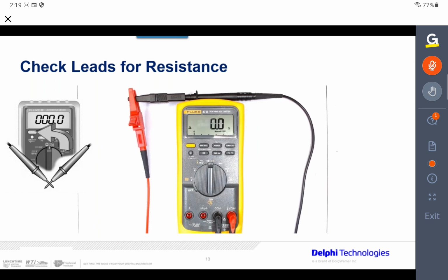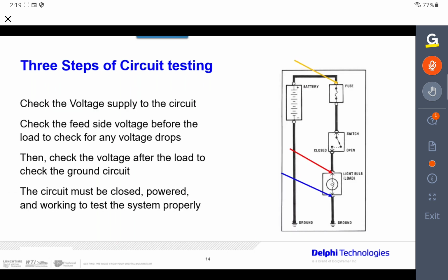The other thing you need to do is make sure the leads are connected together well and pushed into the sockets correctly, because I've seen sometimes the guys get a bad reading because they haven't pushed the leads in correctly. All right, let's talk about 3 steps of circuit testing. This is just my way of doing it. I call it the natural point break of a circuit. The natural point break of any circuit is before the load and after the load. If there's 2 loads, before the first load and after the second load, whatever.